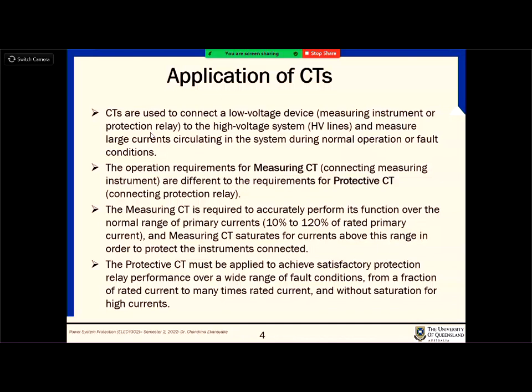There are many different applications when you are looking at CTs, not only for the protection circuits. Basically, as I said, CTs are used to measure currents in a system where you have large magnitudes of current. When you look at the applications in power systems, there are mainly two types of CTs that we use. One is for these protection circuits. Those are called protective CTs.